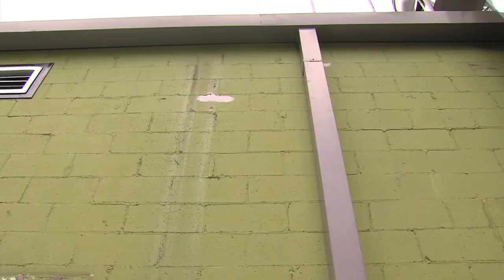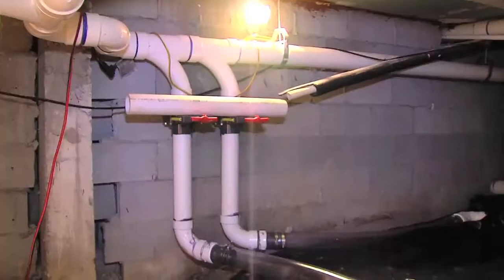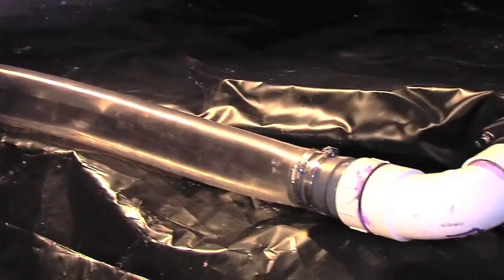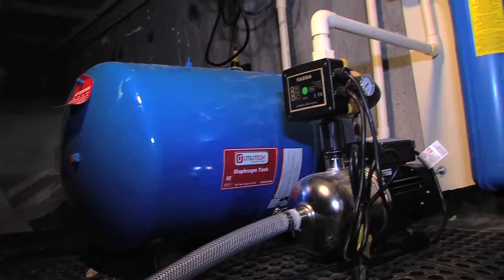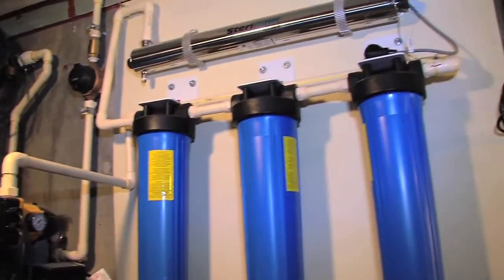Well, the water is collected off the roof. The pre-filter is in the gutter system. There's a gutter guard on it which catches any leaf debris or any granular stuff. It's a gravity fill into the pillow, and then there's two fill ports on the pillow — two 3-inch fill ports. There's an overflow and a pump port. So the water's pumped out from the port and through the pump here, and then it goes through a four-stage filtration system.